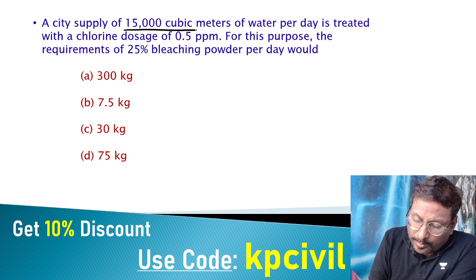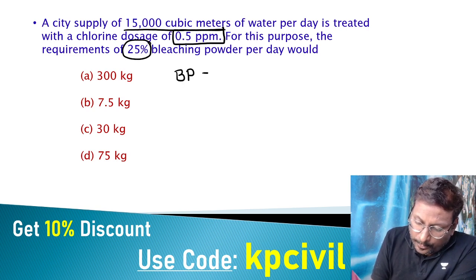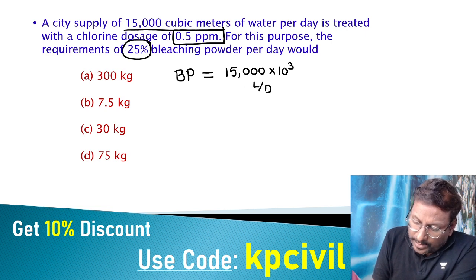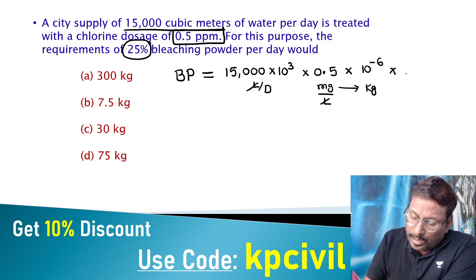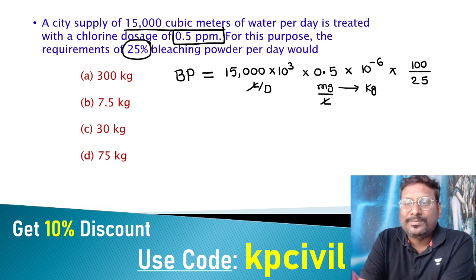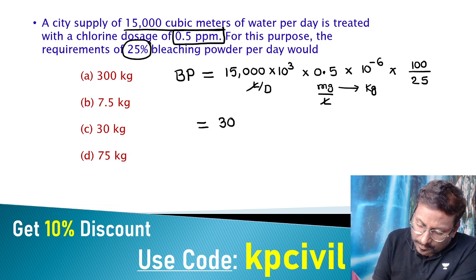A city supplies 15,000 cubic meters of water per day with a dosage of 0.5 ppm. Requirement of 25% bleaching powder: Discharge = 15,000 × 1,000 L/day, chlorine dosage = 0.5 mg/L. Converting milligrams to kg (×10⁻⁶), then multiplying by 100/25, you get amount of bleaching powder = 30 kg per day.